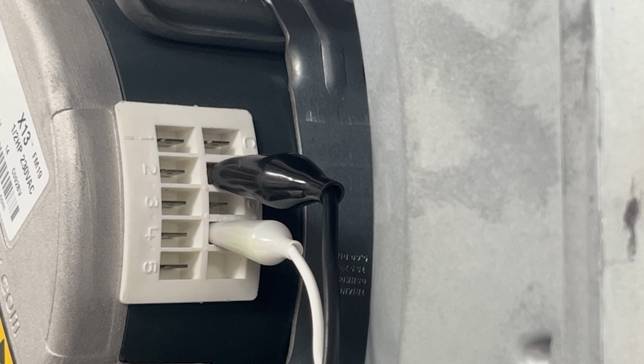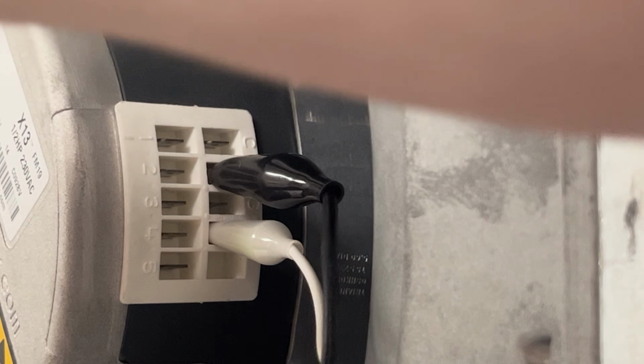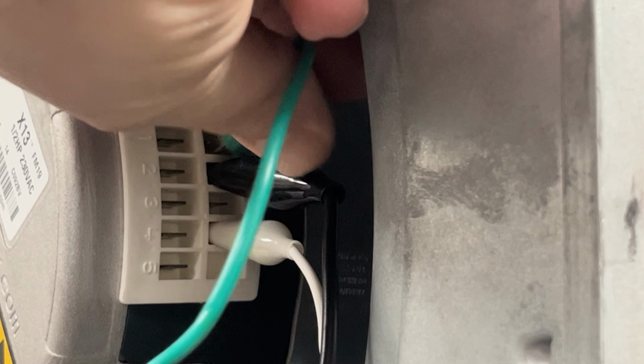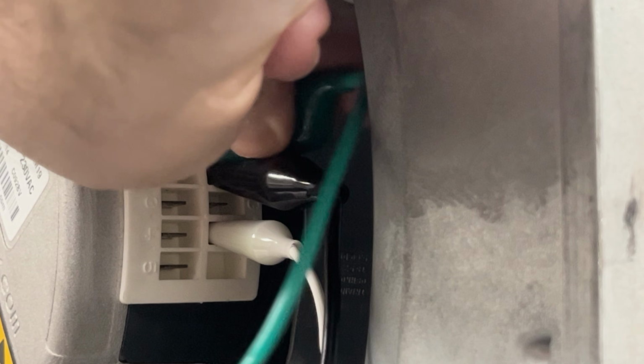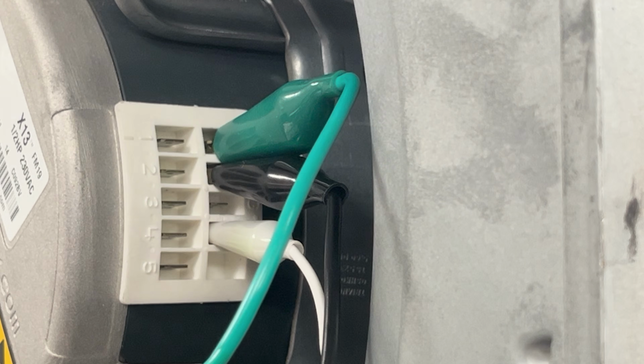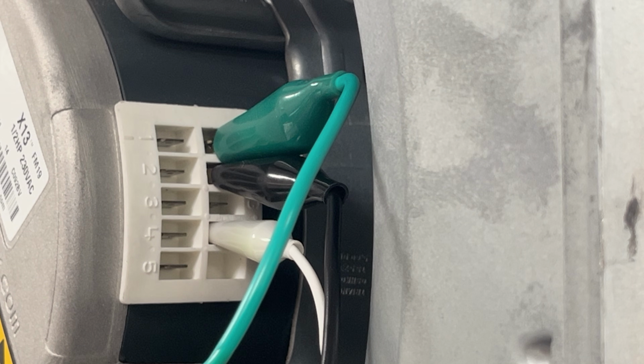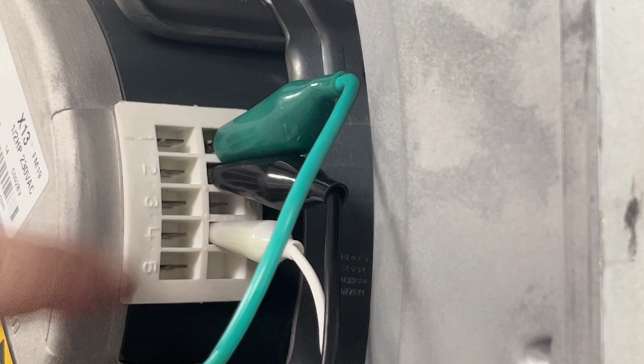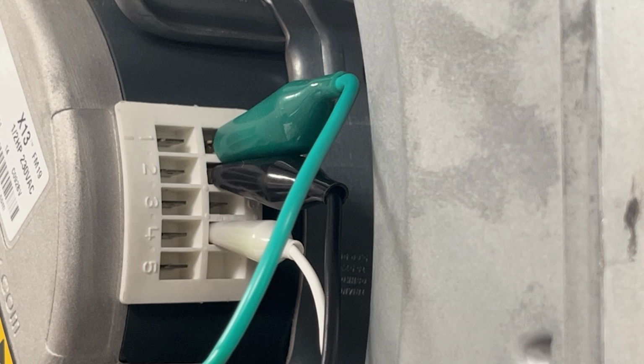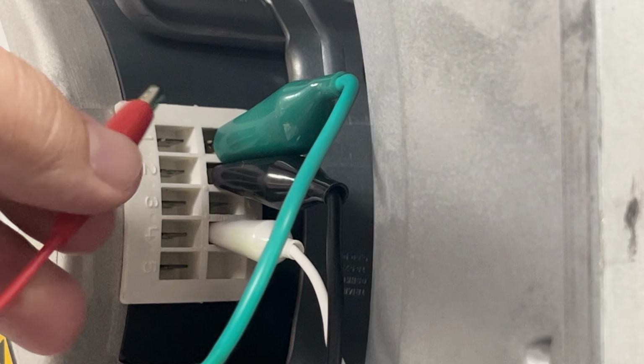So there's my two legs of power. Now we're missing a common. So we're going to go ahead and take our green that we had wired to common earlier. We're going to head and run that back up here, get a good connection. Okay, make sure that's not going to pop off on us. All right, and now we have 1 through 5. So I'm going to go ahead and wire up terminal 1.